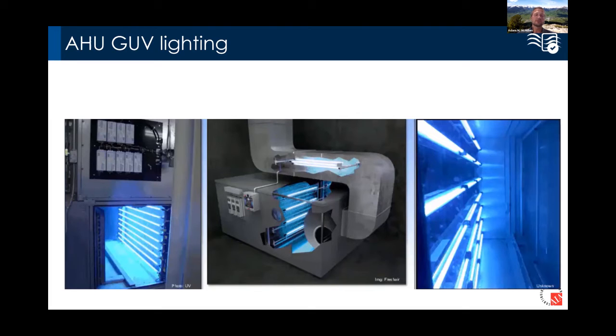The issue here with treating the air is that air will move very quickly through an air handling unit, and in order to deactivate a virus, there's a dosage requirement. Think about it like, you can't go outside for 3 seconds and get a sunburn. You have to stay out there for a while, then the sun will eventually do its job on your skin, right? So if we want to do our job on a virus, we need a certain amount of dwell time where it sees this light. Generally, it just moves through so fast, it can't always clean it all up.